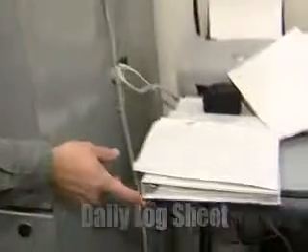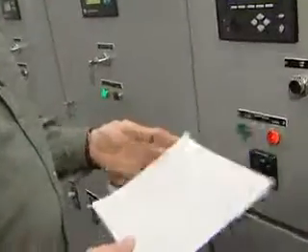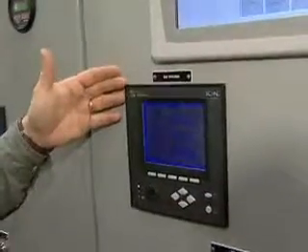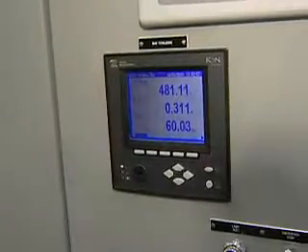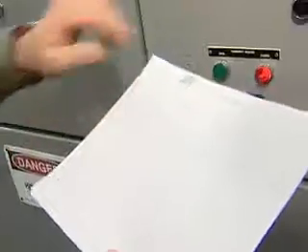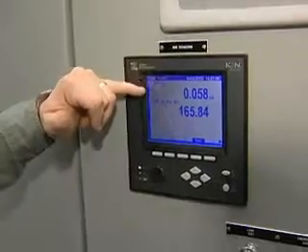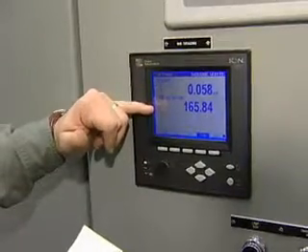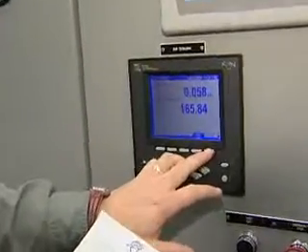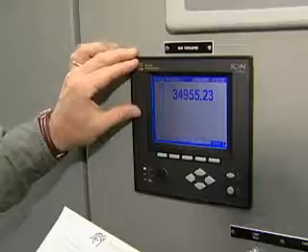At this point, you're going to grab your operator log sheets and start filling out your information. The first thing you're going to look at on your total bus totalizing meter is your voltage, your amperage, and your frequency — those are going to be filled out on your form. From there, you're going to go to your demand KW: the top reading tells you what your KW demand is right now at the current level, and the second one is your peak maximum demand level. The third button is the energy one button, which gives you your KWH — the total amount of electricity that has been generated from this power plant and put out onto the system.